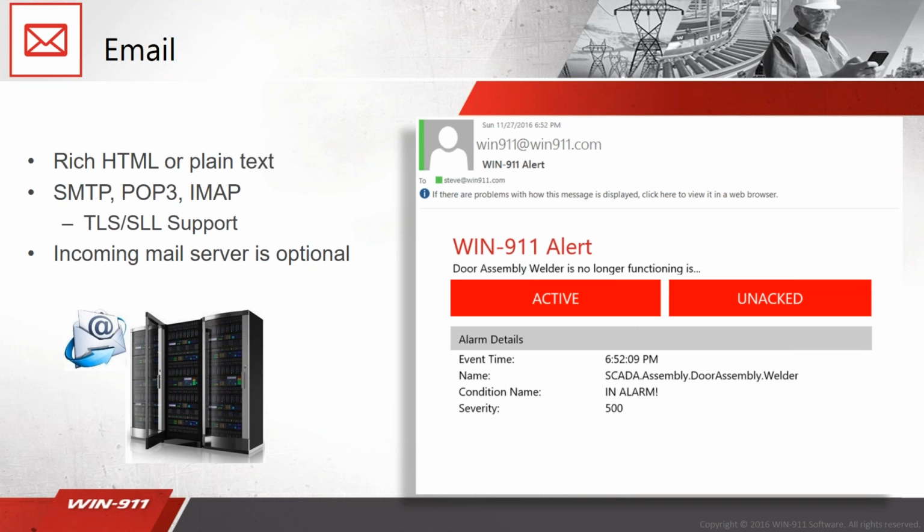It's also good if you're doing the email to your cell phone, like your phone number at vtext.com and so on. We also built in functionality that will allow, if you are doing that, where it's your phone number at vtext.com, you can reply to that, and you can still acknowledge the alarm. We had to do some special plumbing to get that to work, as a lot of the carriers change the formats of the email and so on. So we're supporting SMTP, like I said, to send the messages. We support POP3 for receiving, and IMAP for receiving.